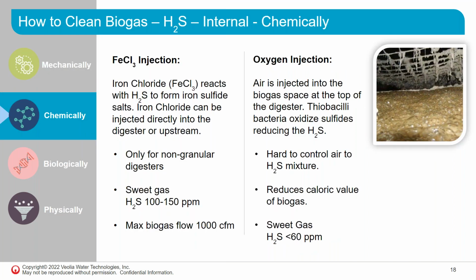Chemical cleaning. We have 2 examples here, ferric chloride injection and oxygen injection. Let's discuss ferric chloride injection. In this method, we actually remove H2S in the liquid phase before it gets into the gas phase. The ferric chloride that you inject reacts with sulfides in the water and produces ferrous sulfide, which is a precipitate. That way you prevent sulfides from getting into the gas phase as H2S.